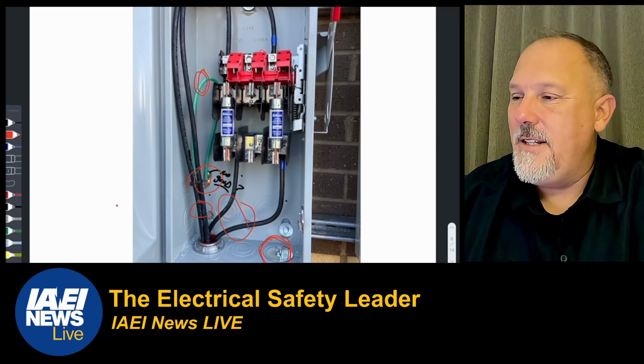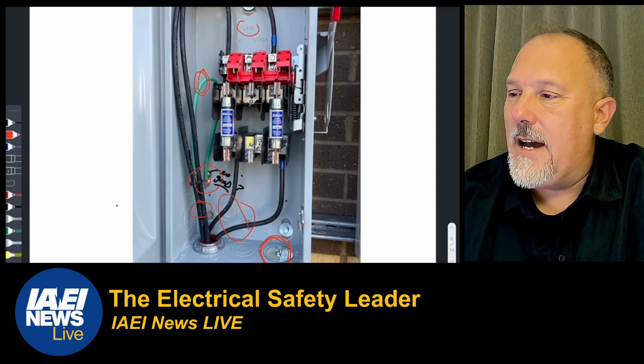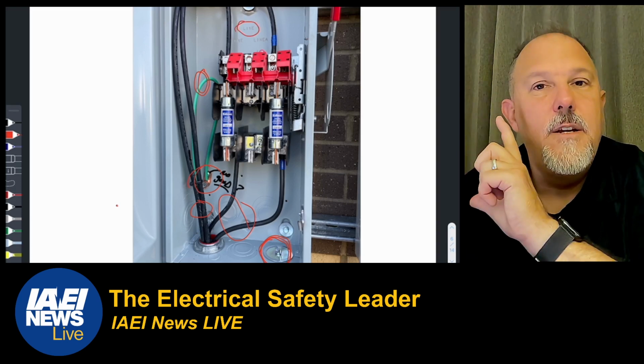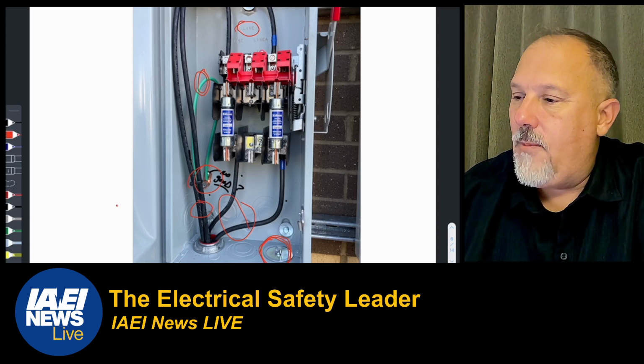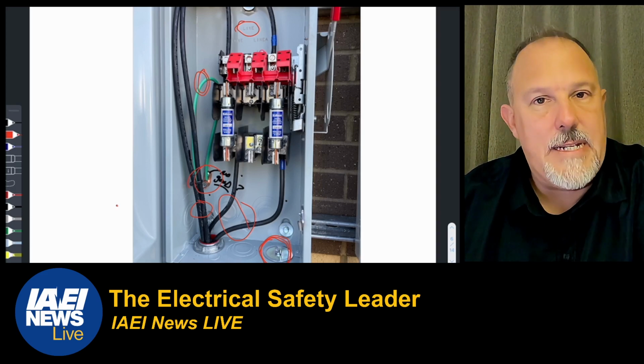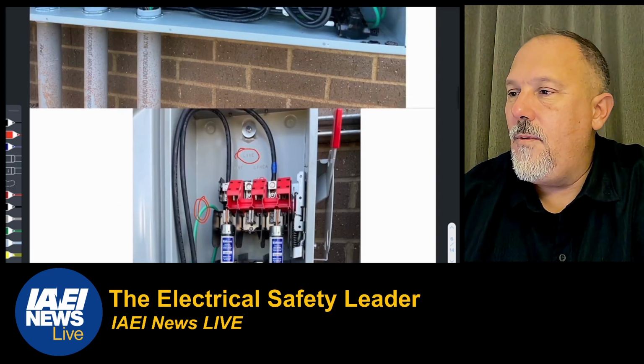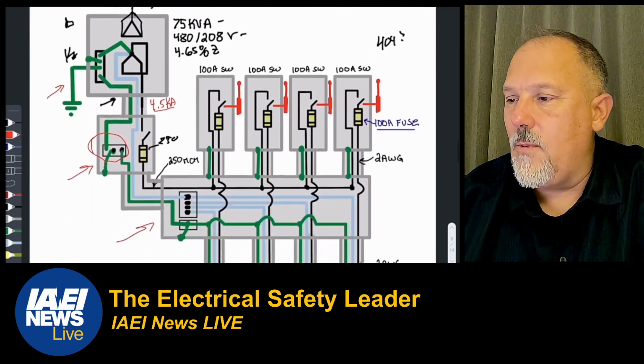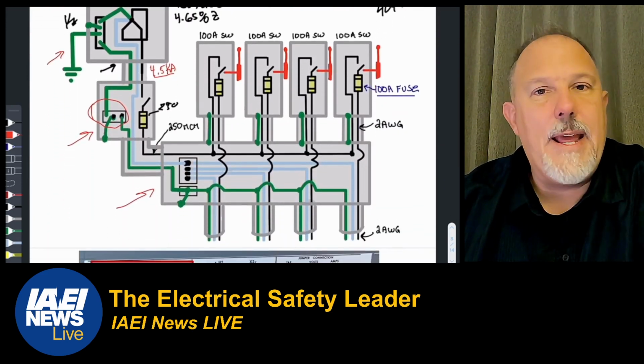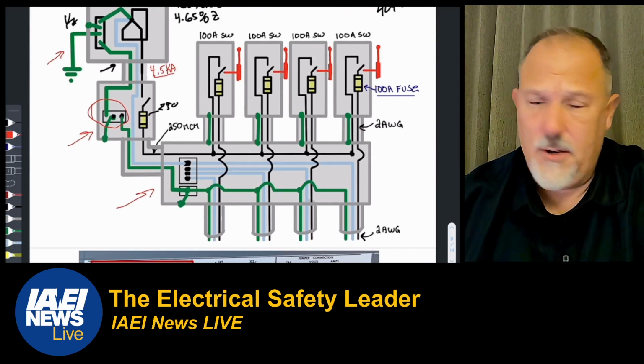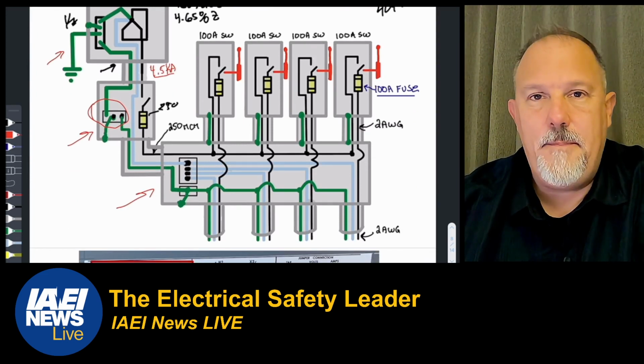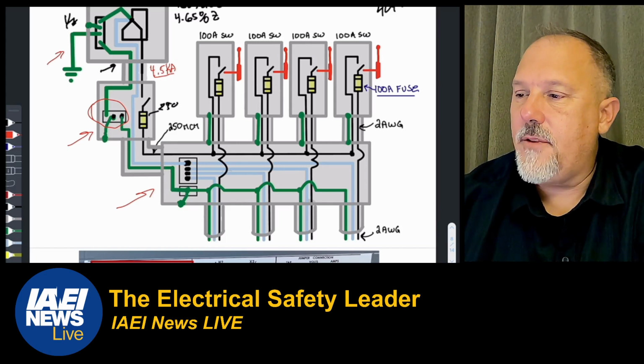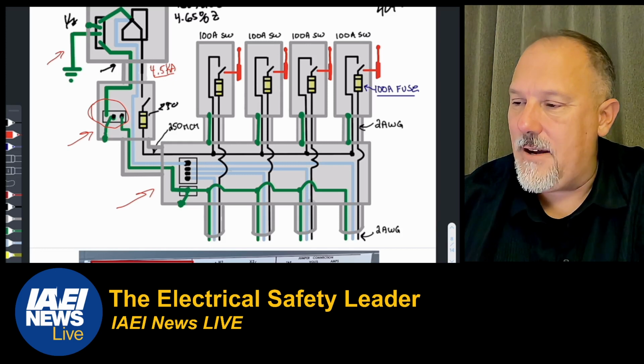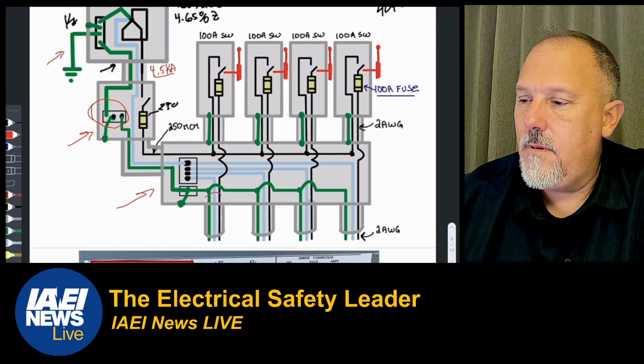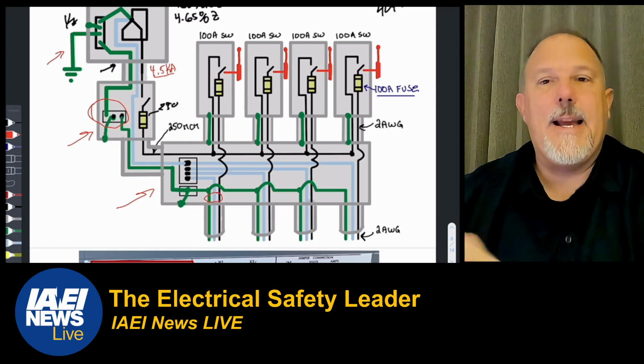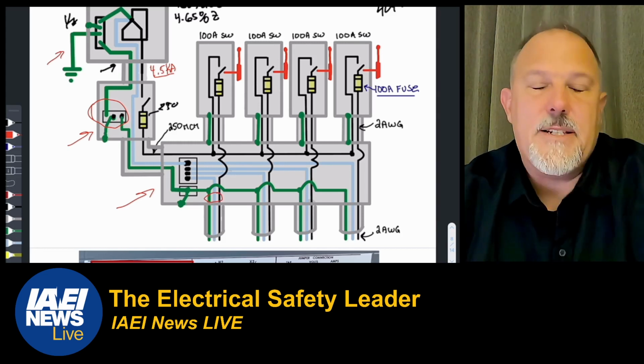Very good, neat installation. And you've got the marking for line. Anything that's marked line and load cannot be reverse fed. What else? So there's no grounded conductor here. So if I look at the one line diagram, they just switched the leg. It's a single phase. So they took the hot conductors up for single phase, took it through the 100 amp switch, back down, and then they picked up the neutral and the equipment grounding conductor and went down to, I guess, the individual dwelling units.